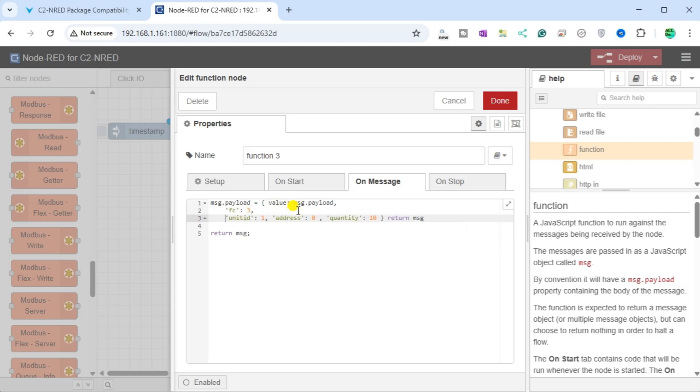We will separate the parameters to make it easier to read. The function code will be 3 to indicate we are reading holding registers. Unit ID will be 1, which we are reading at address 0, and we will read 10 registers. Select Done.